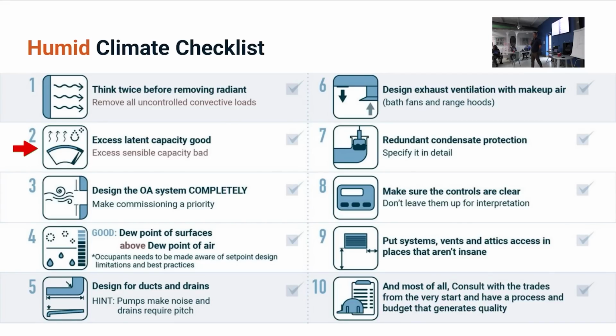This goes back to sizing. If you start looking at sensible heat ratios and all that, for those of you choosing and selecting equipment—choosing equipment with excess latent capacity in your design is good. Excess sensible capacity is bad. You don't want oversized equipment just for the sake of oversizing; you want extra ability to remove moisture.